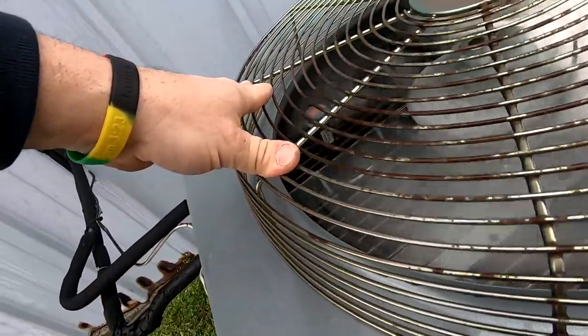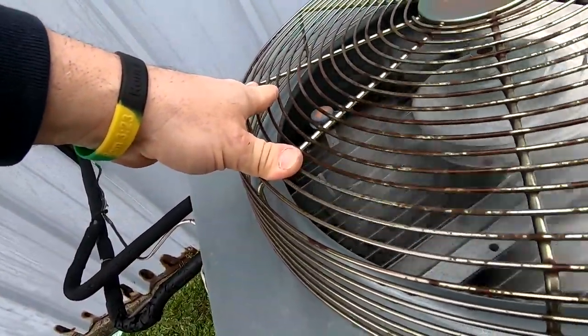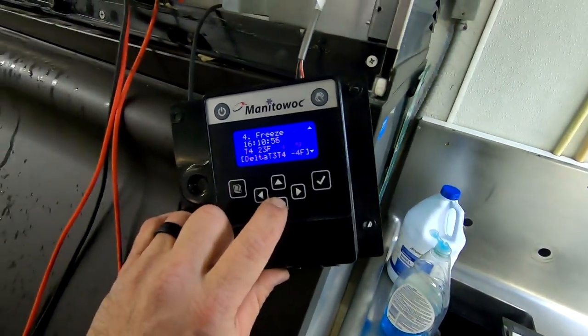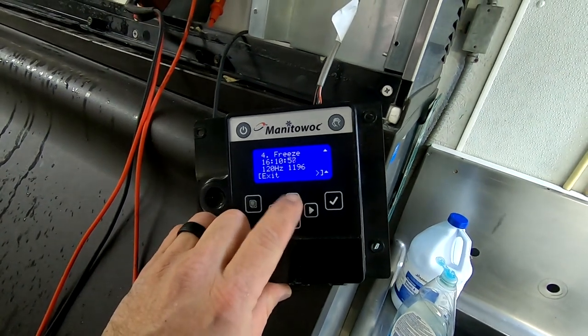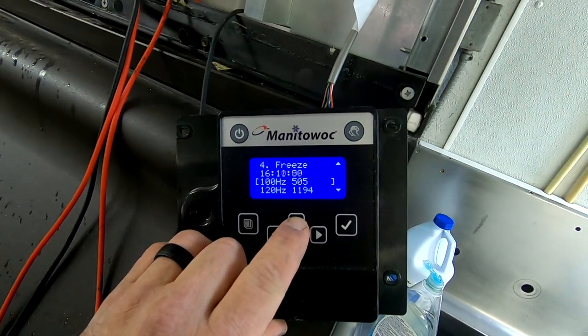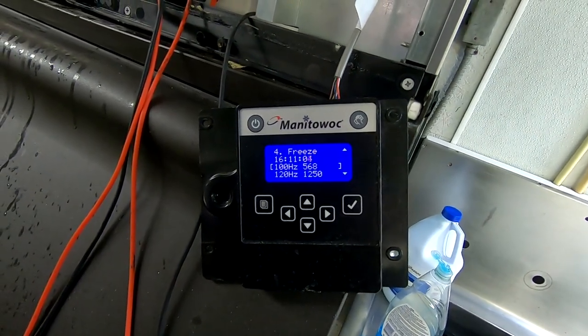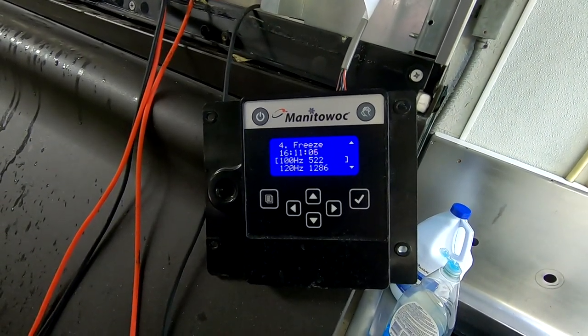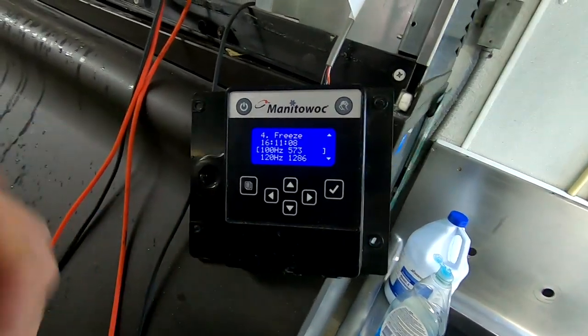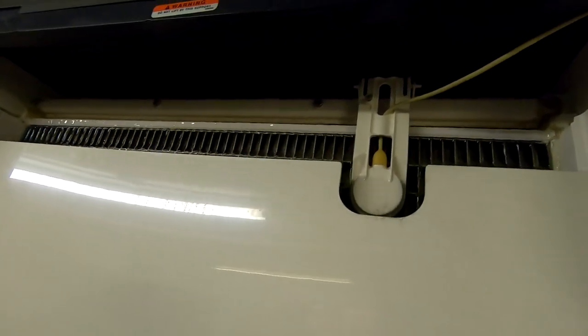Alright, our condenser's out here. Feel some heat on it. Take a look at our coil. It looks fairly clean. Coming in hot, condensing into liquid, going back on the small one. Got your headmaster control right there. It's set up for 225, it looks like.